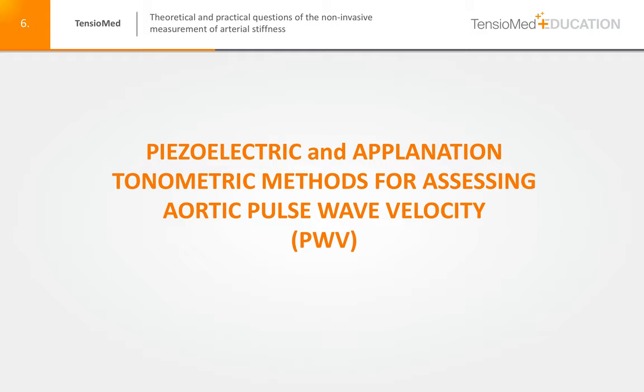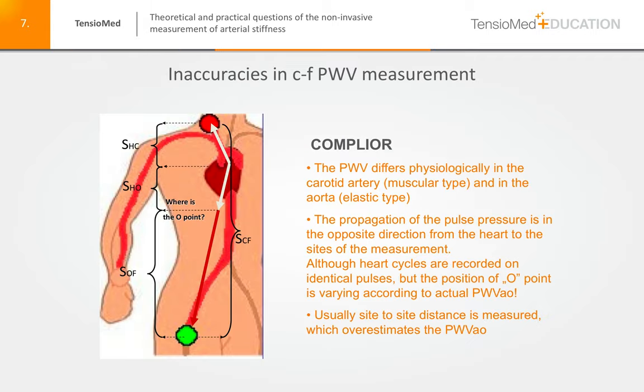Measuring aortic pulse wave velocity, formerly the piezoelectric and applanation tonometric methods were most popular. However, measuring carotid-femoral pulse velocity, inaccuracies and limitations can be found using the piezoelectric method — this device is the Complior. This device uses two sensors, which is seemingly an advantage because we can record the same heart cycle simultaneously. However, the propagation of the generated pressure signal is in the opposite direction to the distance between the carotid and femoral artery. Thus, we don't know what distance is proportional to the time difference measured between the carotid and femoral site.